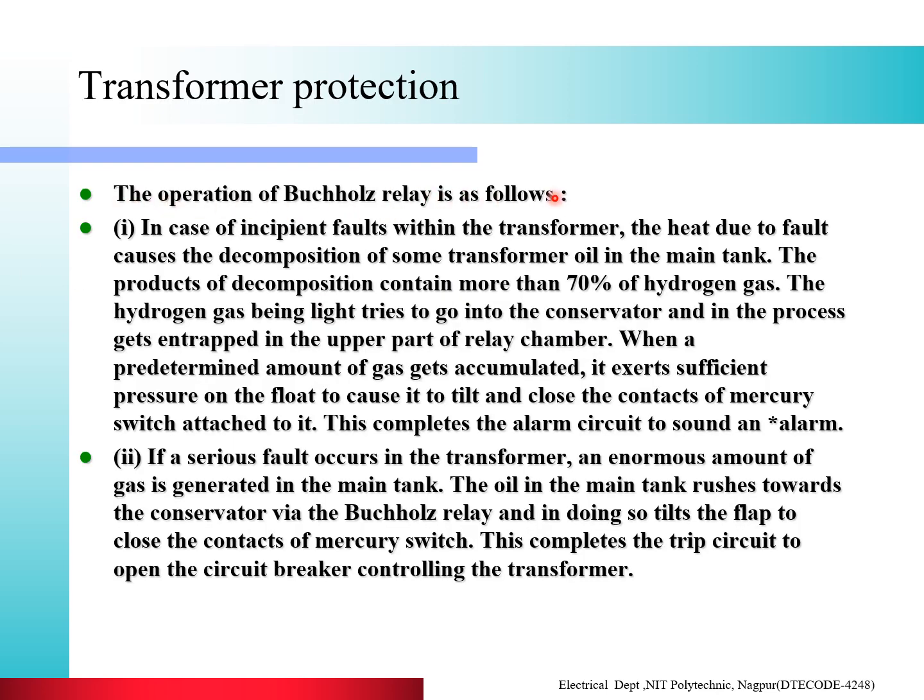The operation of the Buchholz relay is as follows. In case of an incipient fault within the transformer, as we have seen in the diagram, the explanation is given here. During incipient fault, the heat due to the fault causes decomposition of the oil, and this gas contains 70% hydrogen. This gas gets trapped in the upper part, due to which it exerts pressure on the float, and the mercury switch attached to it gets connected. So it will sound an alarm.